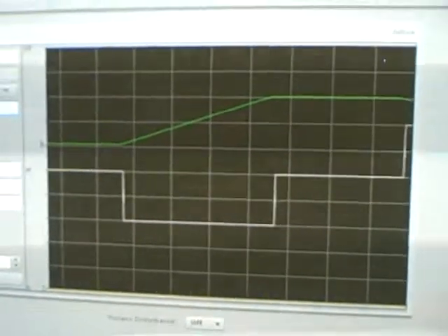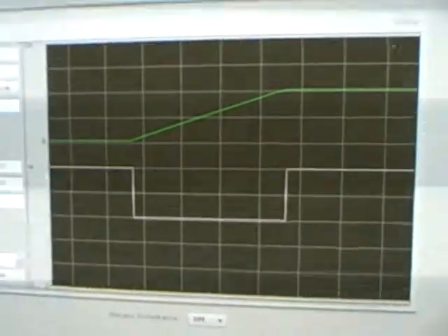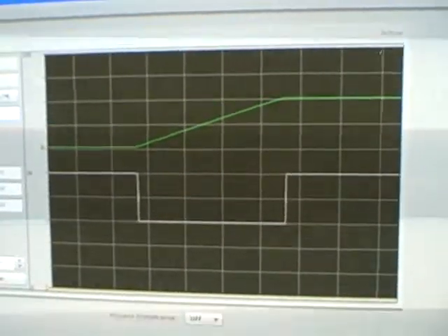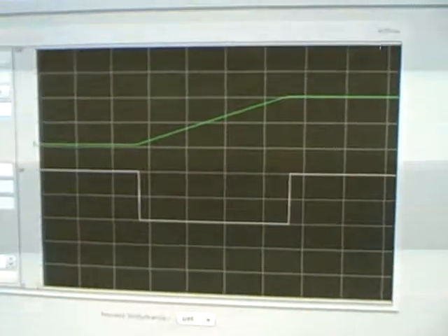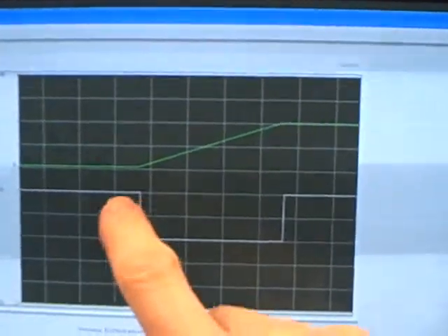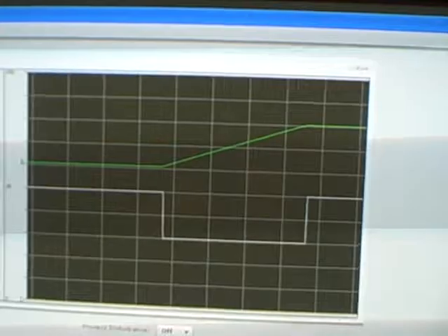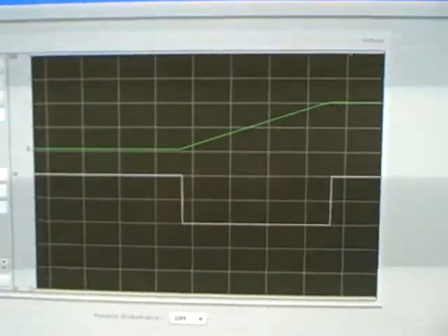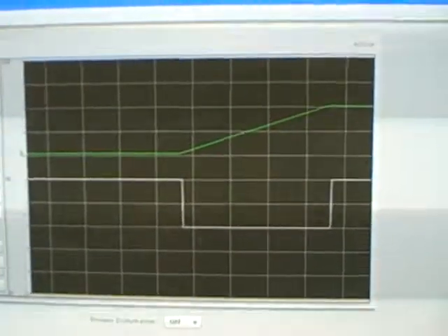To control this, we are going to find that our controller works phenomenally well with a large gain value. Because this process naturally holds whatever set point we want, so long as we go back to our original valve position of 50%, we will find that a proportional only controller does a remarkably good job of controlling this process. We actually do not need integral action to achieve new set point values.